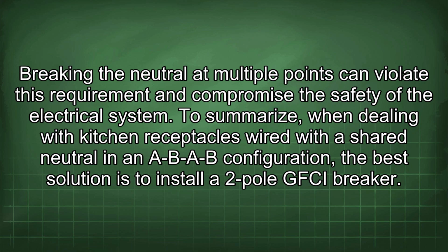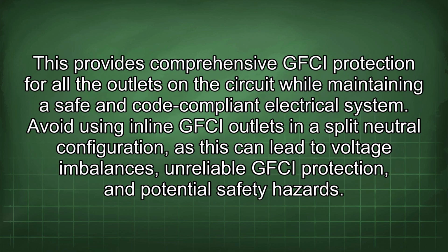To summarize, when dealing with kitchen receptacles wired with a shared neutral in an A-B-A-B configuration, the best solution is to install a 2-pole GFCI breaker. This provides comprehensive GFCI protection for all the outlets on the circuit while maintaining a safe and code-compliant electrical system.